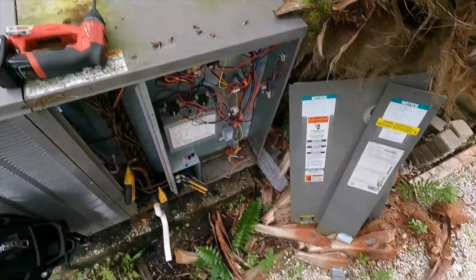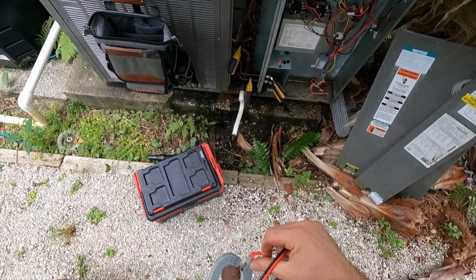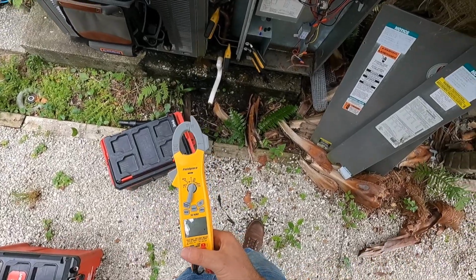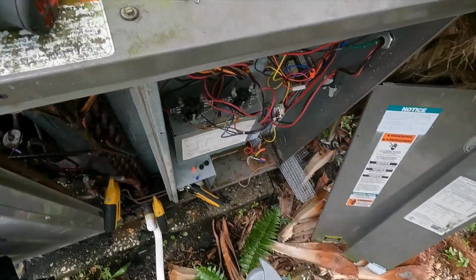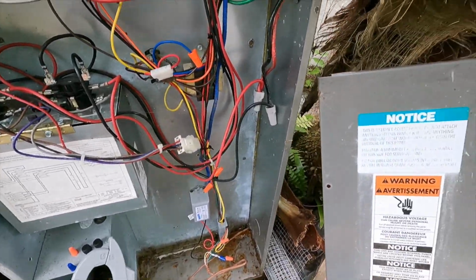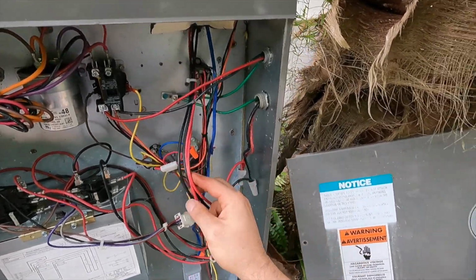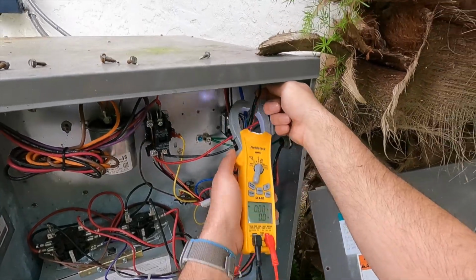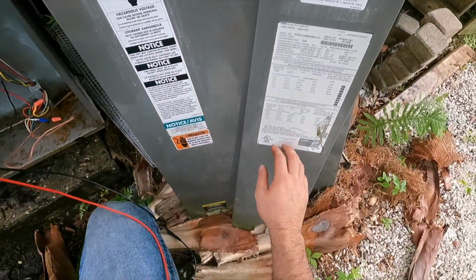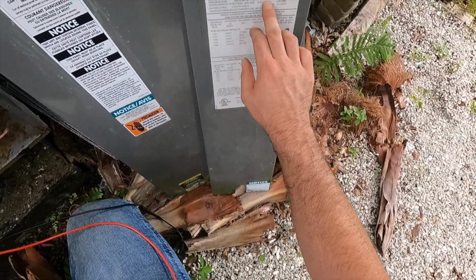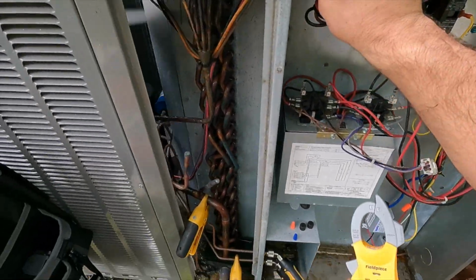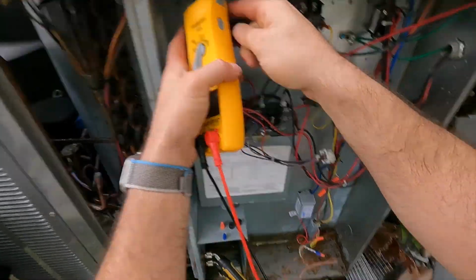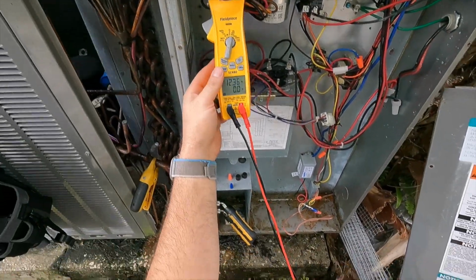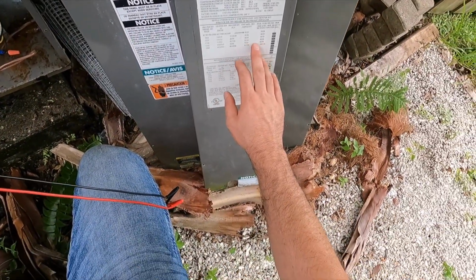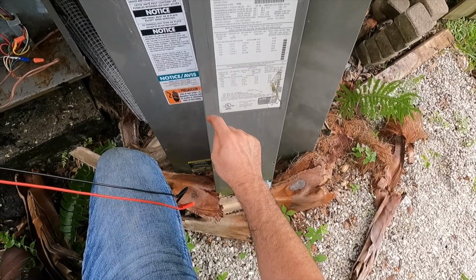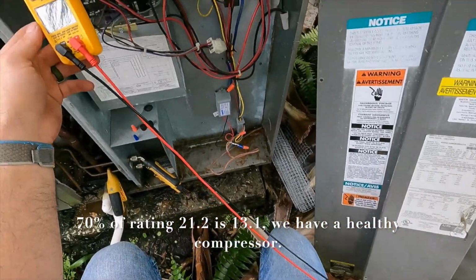All right, so while I let the refrigeration do a cycle, I'm gonna go ahead and take some measurements like our capacitor under load, our compressor run, fan run, and blower run amps. See what everything looks like. So let's go ahead and start with blower is pulling a 3.4. Indoor blower 6.0, so we're looking good there. Let's run off to our fan. Oh, sorry, that's gonna be our compressor. 12.4 on the run. Where you at, compressor? 21.2, so that's looking good.